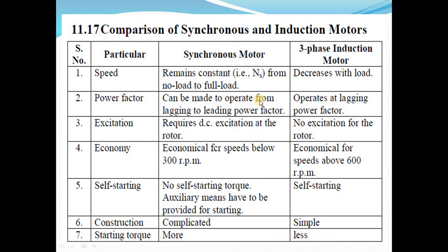The second comparison is power factor. We know that the synchronous motor can be operated from lagging to leading power factor. The three-phase induction motor always operates in lagging power factor. The third comparison point is excitation. The synchronous motor requires DC excitation at the rotor, whereas in the three-phase induction motor, no excitation is required for the rotor.